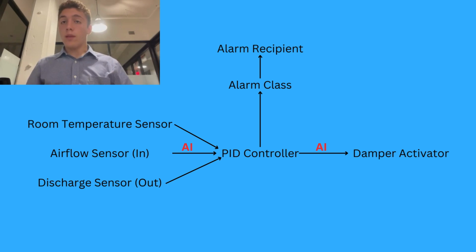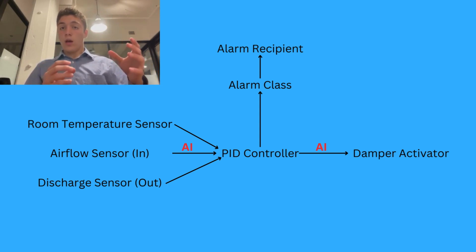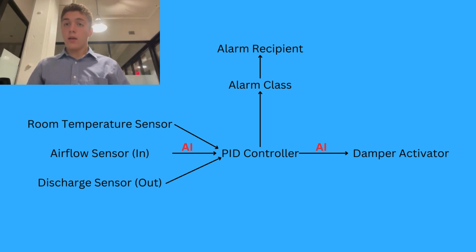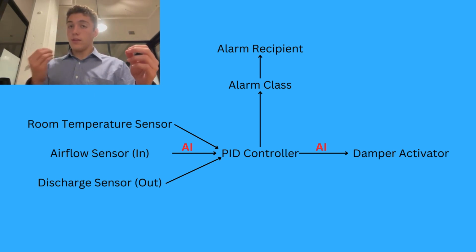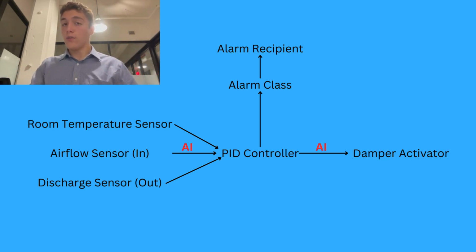So different pieces of equipment need different types of data to work. For example, you wouldn't be able to link a sensor with a temperature reading, which is an analog point, with a fan that can be only turned on or off, since the sensor has an analog output, or AO, and the fan has a binary input, or BI. Therefore, you need a function in between to tell the fan whether or not it should turn on or off based on the analog input. Therefore, I'd use a T-stat in this case, since it could compare the temperature reading with the desired temperature and then turn that into a binary input to tell the fan whether or not to turn on or off.